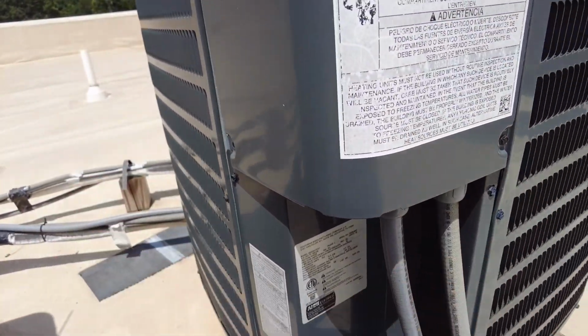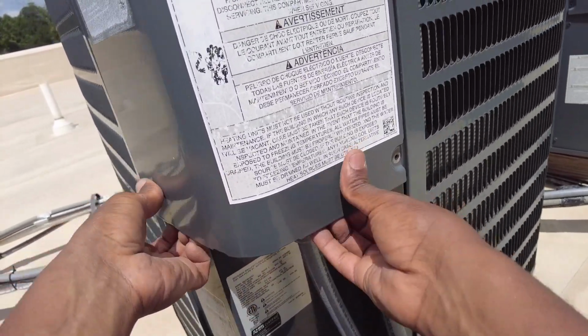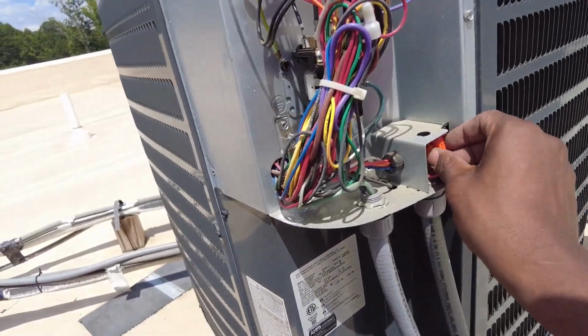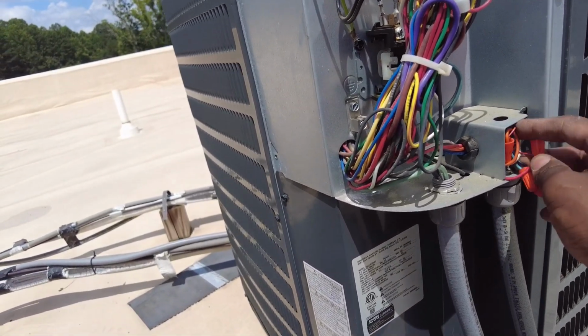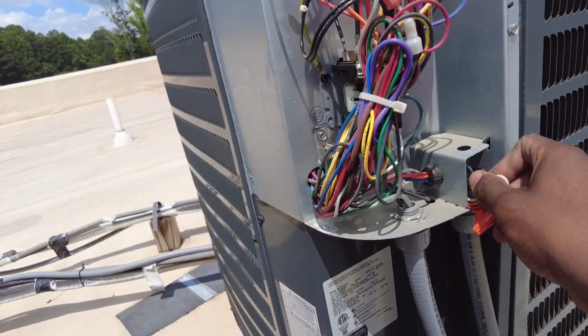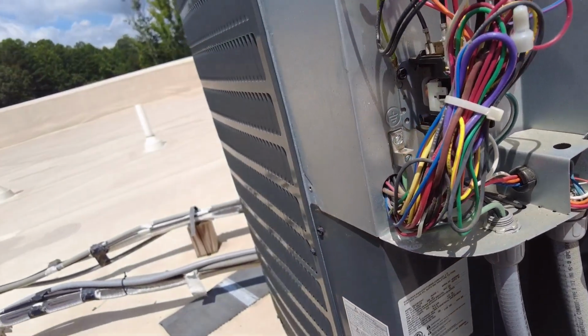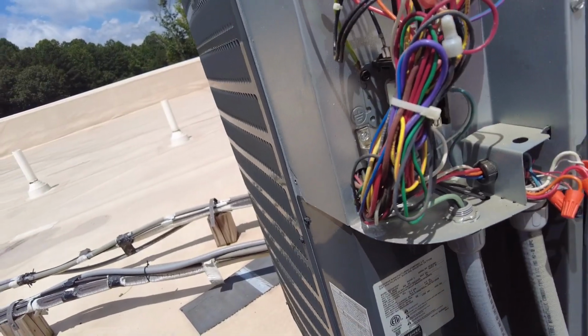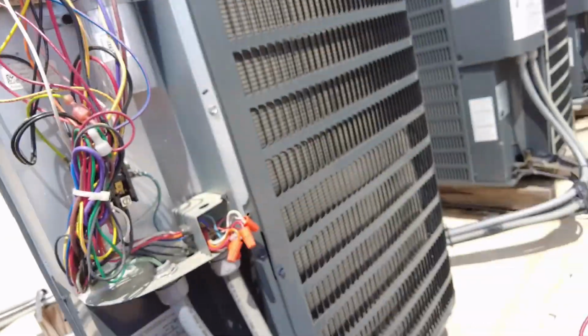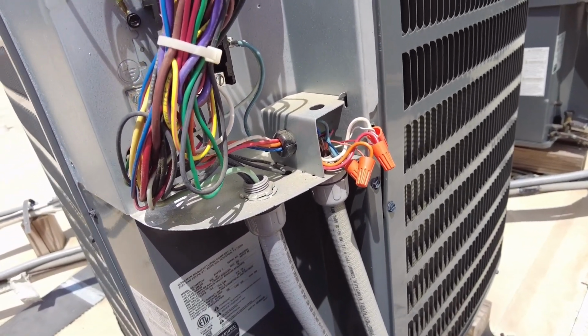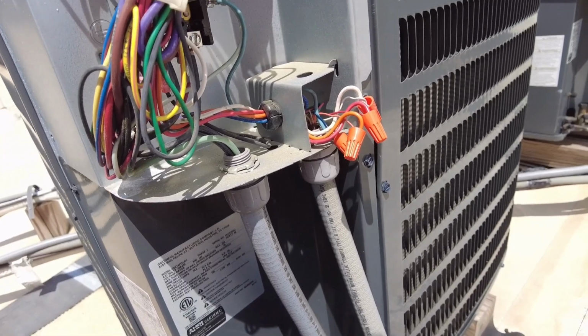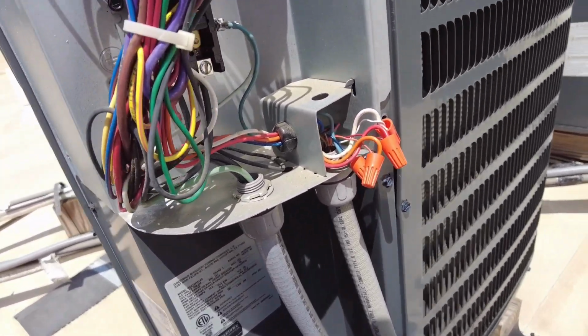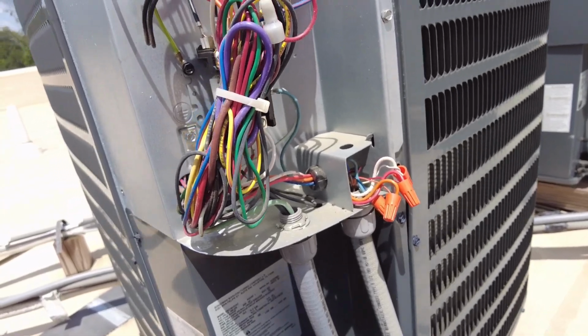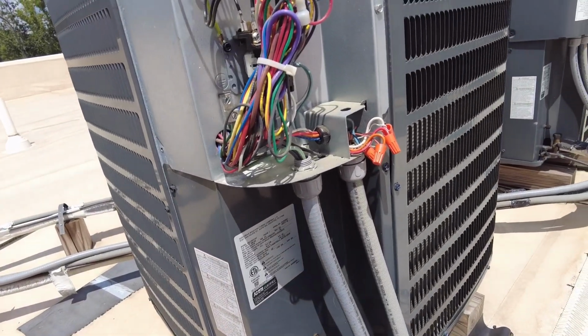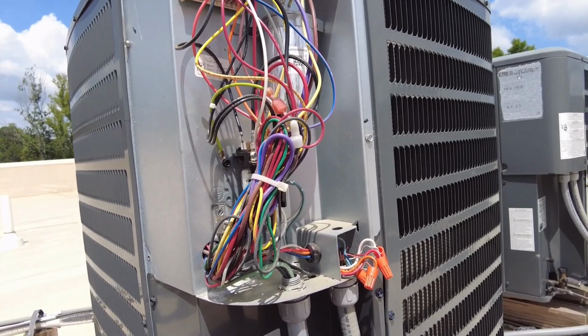It's just like a baby short, meaning it only manifests gradually. It doesn't just immediately blow a fuse, or it's slow enough to kill the transformer. So anytime you got a short that will kill your transformer, that means it's constant amperage, constant low amperage, not enough to actually trip the fuse, but over time, sending that voltage as it's always drawing through the windings, it'll slowly melt that lacquer off the windings and your transformer gets burnt up. So let's see if we can start to trace this thing.